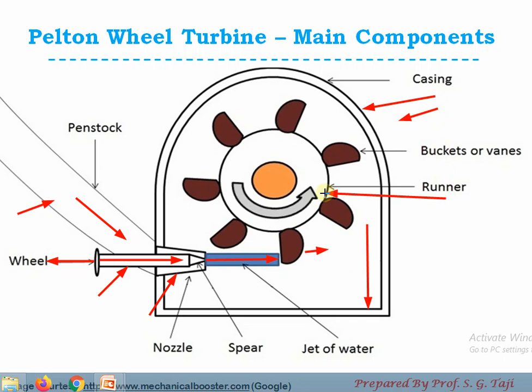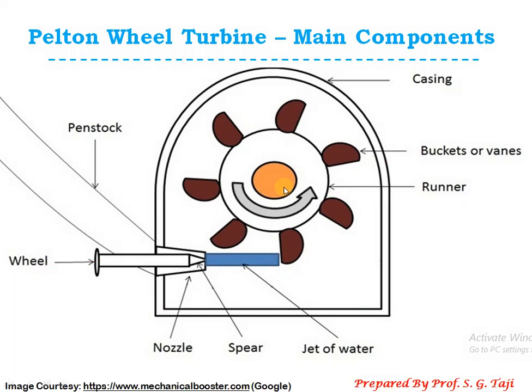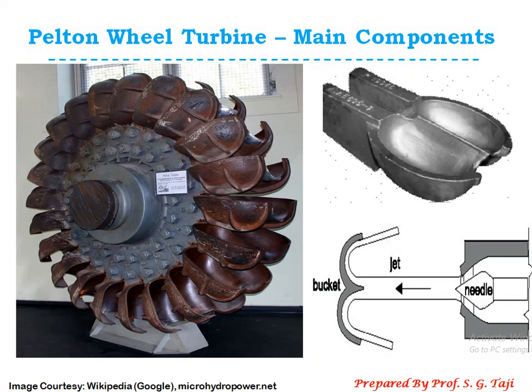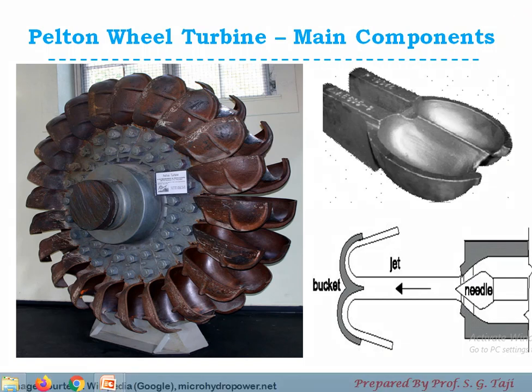The next component is the runner, over which all the buckets and vanes are mounted. The runner is the circular disc on which all the buckets are mounted with even spacing apart. This runner is coupled with the shaft at the center. Whenever the jet of water strikes on those buckets, the buckets get displaced, and as those buckets are mounted on the circular wheel (also called the runner), rotational energy is produced. This rotational energy is taken by the shaft and transmitted to the electrical generator where it is converted into electrical energy.